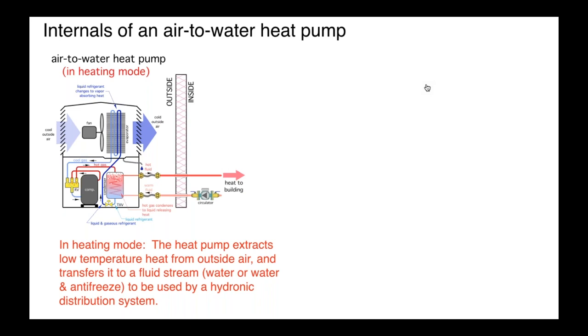If you have never heard of an air-to-water heat pump, it is a machine that in heating mode, let's say we're in the winter, we're basically extracting low temperature heat from outside air by blowing air across an evaporator coil that is part of a refrigeration system. See it here. And we're upgrading the temperature of that heat using the refrigeration process. We're sending that gas into a compressor. We're bringing up the pressure and the temperature.